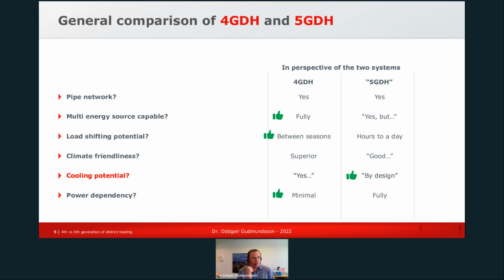So now, if we go to the multi-energy source capability, then there is a difference. In the fourth generation, we are fully capable of using whatever energy sources are available. The same applies to the fifth generation, but it has the catch that if we run with a too high quality energy source, we are essentially suffering on efficiency, because we need to run the system with a low temperature so we are not losing most of the heat.